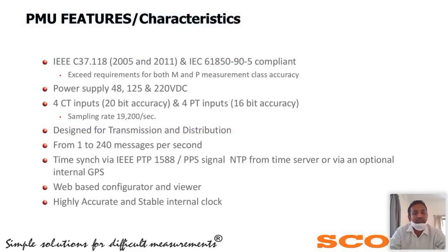These are all the features a PMU must have, like IEEE C37.118 compliance of 2005 and 2011. Our PMU will support both editions, and 2014, the new edition, also. It also supports IEC 61850-90-5 compliance.